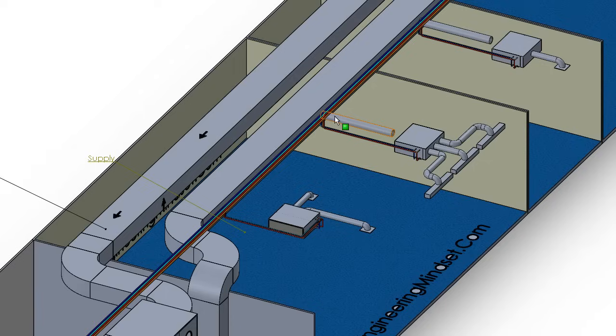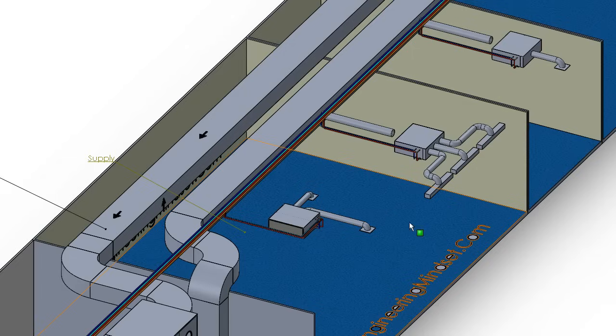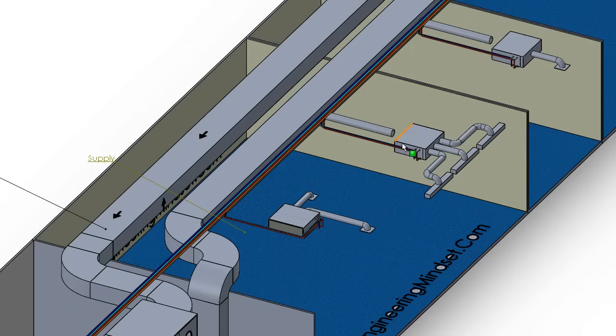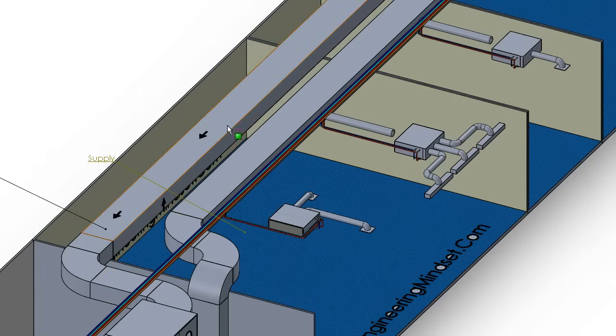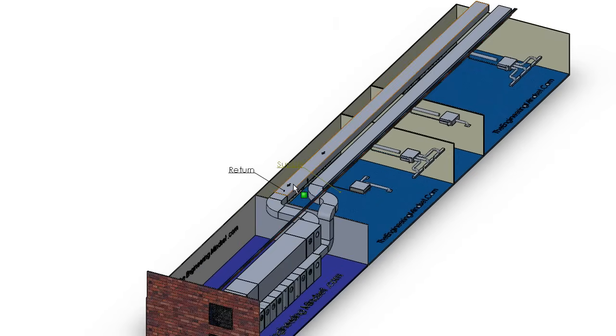This fresh air is directed into the inlet of the fan coil unit — it's usually not connected directly; there's a gap between them, which we'll look at later. The fresh air enters into the box, gets sucked inside by a fan, then gets heated or cooled and pushed out through diffusers into the space. Some of the air will recirculate up through the false ceiling grills back into the box, while some will be picked up into the return duct and pushed out of the building.